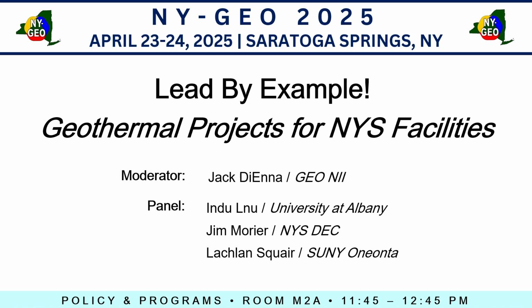St. Patrick's Cathedral has 12 standing column wells, 1,200 feet deep. They've got to backflow those heat pumps once a month, so maintenance gets pretty heavy. So unless you have, like you said James, something that you hit and can use, and the keyword is free, open loops are not very well received in most places.